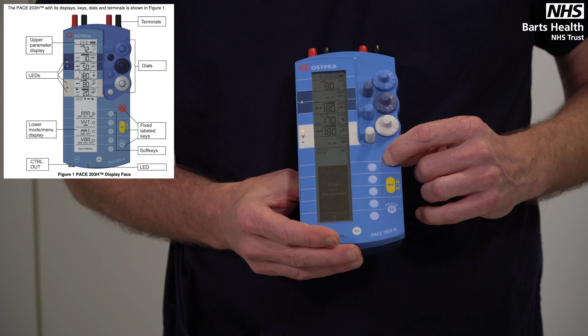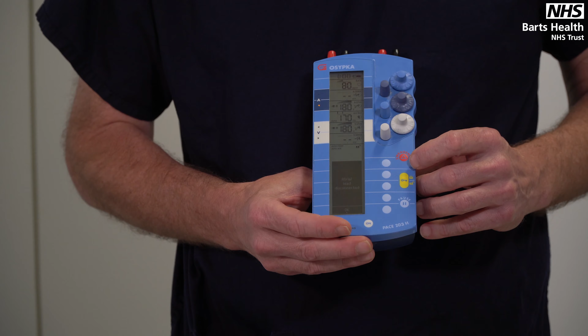Okay, the next important button on the front of the pacemaker is this red button. That's the emergency pacing button, and what that does is it switches the pacemaker to a non-sensing mode, and it puts up the output to maximum to hopefully overcome any problems with connectivity with the patient. So by pressing that, it goes up to 18 on both the atrial and the ventricular outputs.